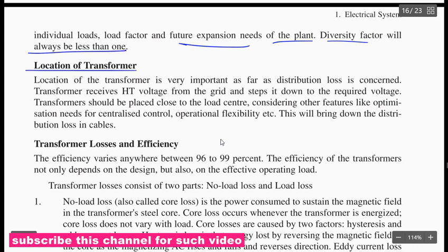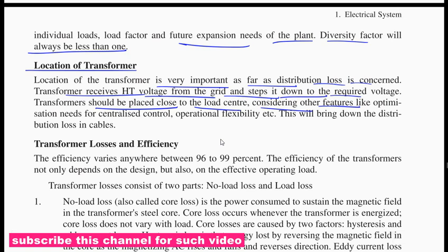Location of transformer. Location of transformer is very important as far as distribution losses are concerned. Transformer receives high voltage transmission from the grid and steps it down to the required voltage. Transformer should be placed close to the load center, considering other features of the layout optimization. This will reduce the distribution losses in cable.